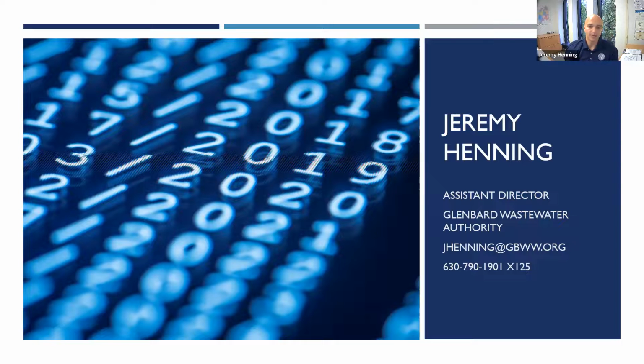What might happen is it just has a basic counter, and it's not telling us runtime necessarily for these filters, and it would get stuck. So a couple of the instances, maybe towards the end of the day, would actually just never turn off. Instead of just having a 20 or 30-second backwash time, it would actually just sit and run because it was never clearing and getting back down to its set point. So another intermediate step in the meantime was to increase that set point a little bit and allow it to get back into a zone that was more comfortable.